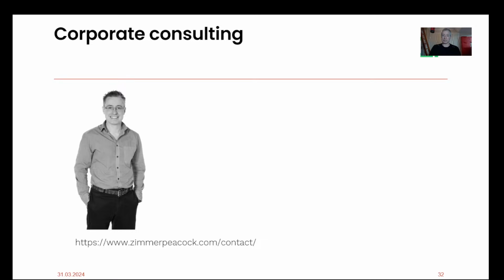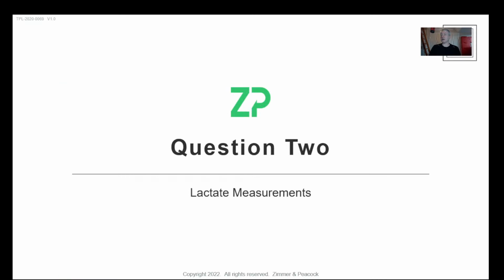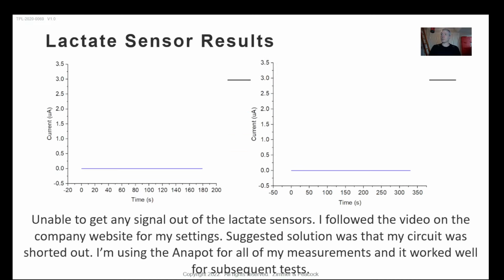So I think people do need advice earlier on, otherwise they're going to unfortunately repeat the mistakes of the past. Question number 2, somebody's got a problem with their lactate sensors. I've got a suspicion they've actually got a problem with the instruments, so we're going to have to take a look at this. But when I look at their lactate sensor, it's meant to be running in an amperometric mode. So this looks flatline to me. Flatline means there's some sort of breakage on the counter electrode.